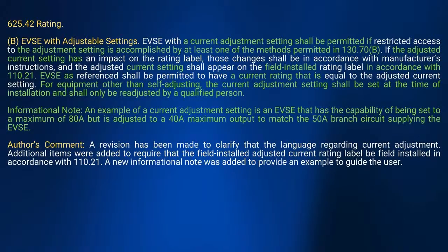To me, I think it's so stupid. Just to give people some color on this, they have a little adjustable wheel in there, and when you're installing it you set that wheel at a certain ampacity. For example, I did number 8 on a 50 amp breaker. I didn't add 125% or anything, and it was already baked into the unit. It said set the dial to 50 amps, close it up, set it and forget it, and your charge rate is at 42 amps.